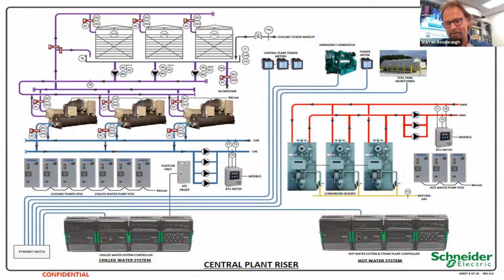So here's a good example. In a specification for your building management system, there's usually one line item written in there, under the mechanical side, that basically says: upon power failure, start critical equipment once the generators have come on and you've transferred over. What does that mean?